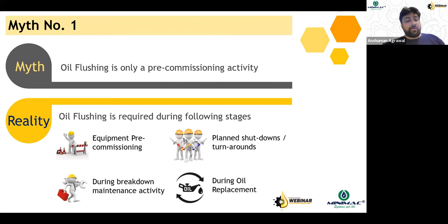It's also a part of your shutdown and turnaround activities. Flushing is also required during breakdown maintenance. Suppose you have a sudden breakdown in your equipment and need to repair parts, dismantle them, and reassemble them - even during those activities you need flushing. And whenever you plan an oil replacement for your entire system, whether upgrading to a different grade of oil or changing the entire oil because it has degraded or for some other reason, you need flushing. So flushing is not just a pre-commissioning activity, but is required throughout the life cycle of the lubrication system.